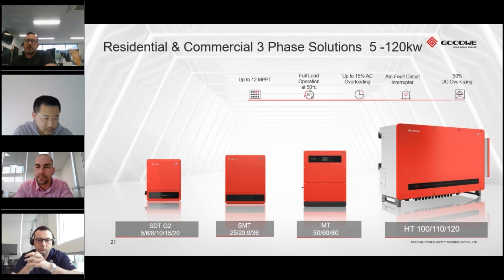It has 2 MPPTs, and it also has 2 inputs per MPPT. So if you're familiar with the older version, which is the 10, the 15, and the 20, it's also had 2 trackers, but it only had 3 inputs in total. So this basically gives us a lot more flexibility, also gives the installer greater oversizing ability as well. And some of the key differences between the new version and the old version, I'll go through in the next couple of slides.